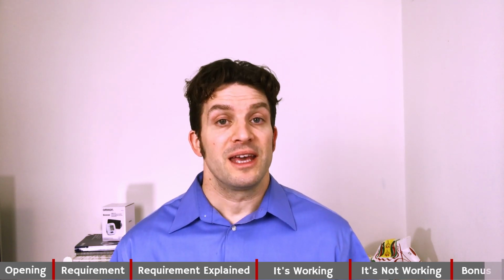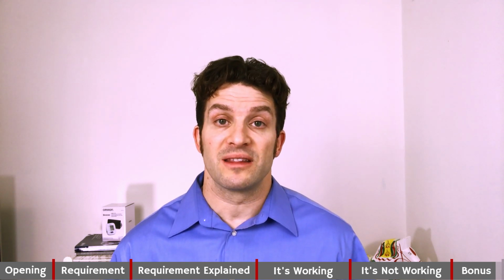Now for the 3 bonus questions. First, how do we ensure or how do we trace all design outputs back to design inputs? Second, you should always ask this question as part of any review of design verification. Were there any deviations? Third, if there were deviations, what is the risk of that deviation? What's its impact on the validity of the validation itself or the verification? And how was the deviation dispositioned?